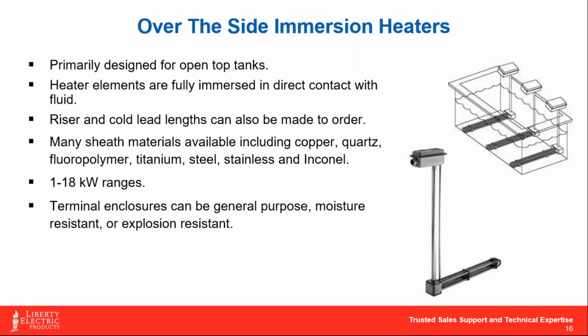So an over-the-side immersion heater is exactly what it is. I think we found a couple of pretty good graphics to put in with this slide as well. We don't see quite as many of these as we used to when we had a much more robust industrial segment. This is a product that is used pretty much specifically for open top tanks. And they're popular in plating operations, or places where, again, you've got chemical dip tanks.